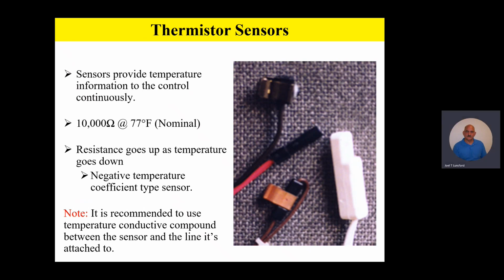But if you were to take some saran wrap and put it on that sensor and put it in a glass of water that you knew was 77 degrees, and then take your volt ohm meter, set it up for ohms, and read the ohms on that sensor, it should be very, very close to 10,000 ohms at 77 degrees. So this is a really neat way to make sure that these sensors are in calibration.